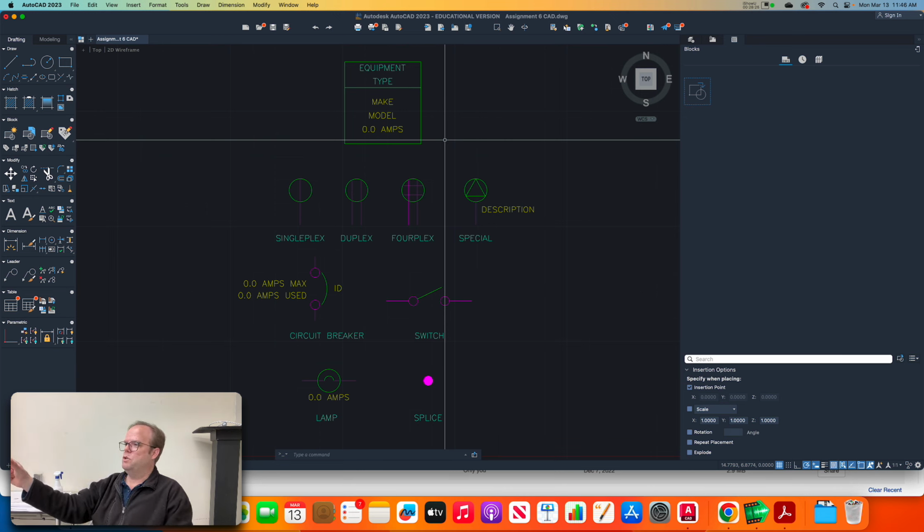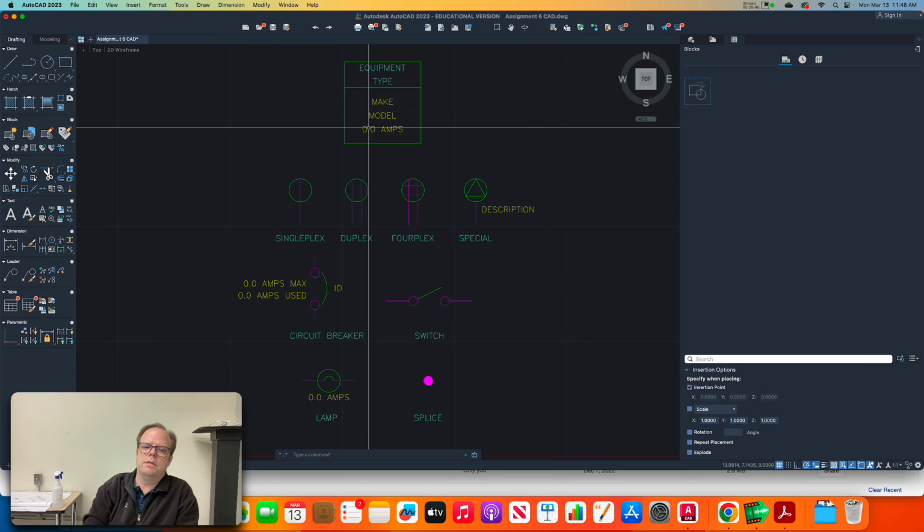A lot of people get confused with power amps because power amplifiers will also be specified in watts, but the watts is like the output of the amplifier, and that's against a certain impedance, and that's not what you're looking at. You're looking at the power supply for that amplifier. How many watts is it capable of? And that gets you the current. So anyway, you want to put the number of amps that is the worst case scenario.